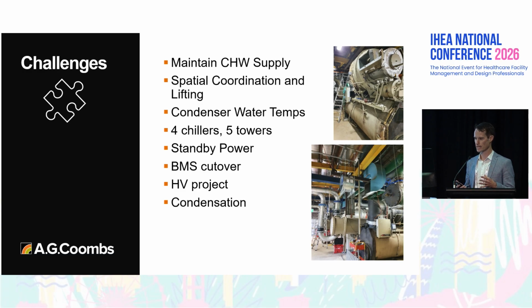The spatial coordination was incredibly difficult, so kudos to Wattpac for managing that. Effectively that meant we had to break the project into 4 discrete stages - each stage was 1 chiller, and we needed that chiller back up, running, stable and reliable before we even touched the next one. So it was basically taking a chiller offline, lifting it out, putting the new one in, sliding it into place, commissioning it, and then doing that all over again 4 times.